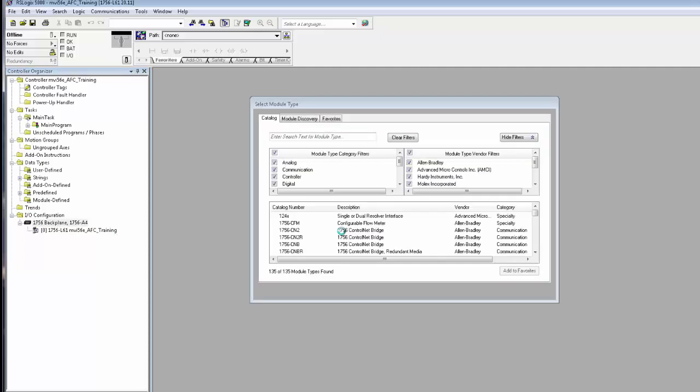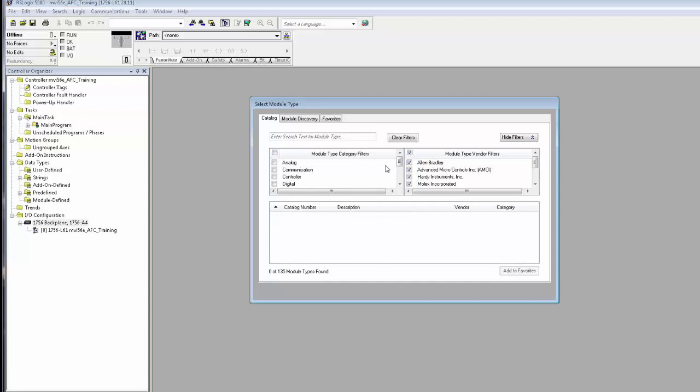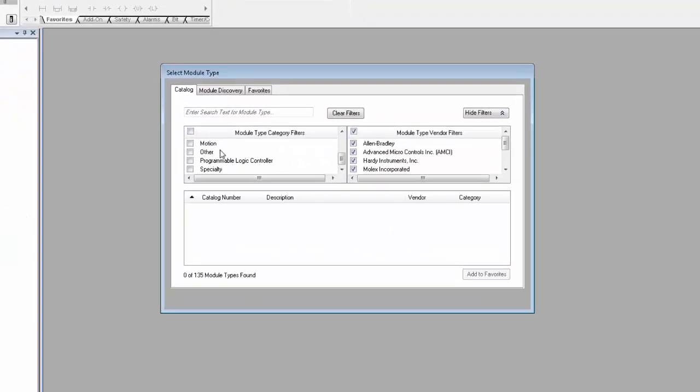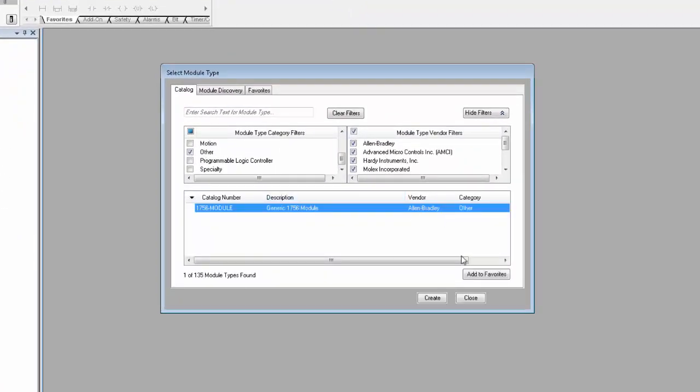In the Controller Organizer menu, expand IO Configuration, select the 1756 backplane, right click and choose New Module. We'll select the generic 1756 module and click Create.